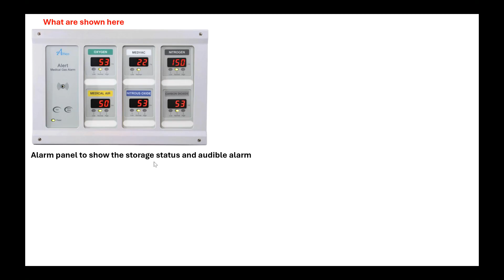If you go tomorrow and see in your theaters, everywhere in the main OT outside, you will find these machines. If you are using all these gases, you will find there will be a display. This has normal pressure, green light will be there. If it is totally empty, it will give a red light and also produce an alarm. As the pressure is dropping, it will show an amber color. So this is a warning system. This is the warning panel or alarm panel to show the storage status and give an audible alarm.